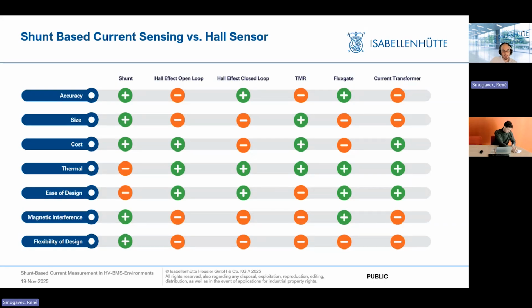Mostly a clear-cut answer is given because of the possible currents that occur, with either resolution. So if there's something in the kiloamp range, the two-digit kiloamp range, shunts are not really able to work with that, so it has to rely on a different solution. Therefore, there's rarely a gray area between Hall effect and shunt. And most companies strictly use one because they build up experience with it and get a better understanding and better accuracies out of it.